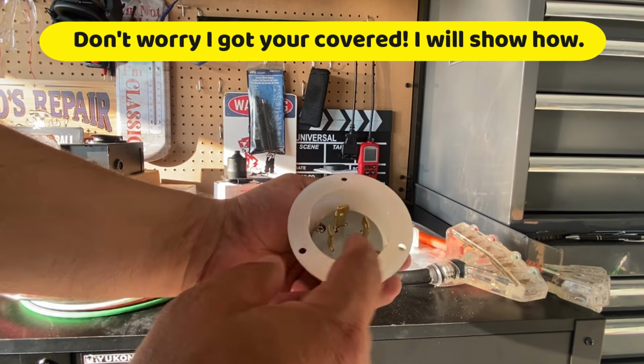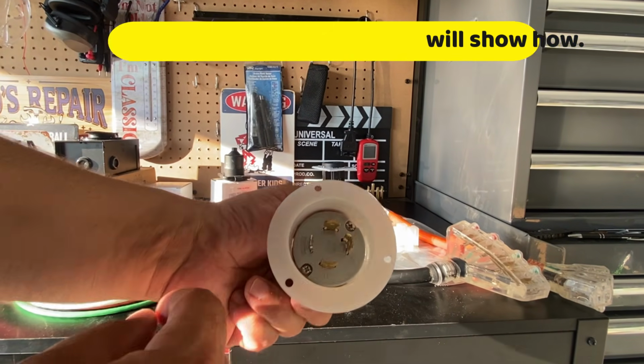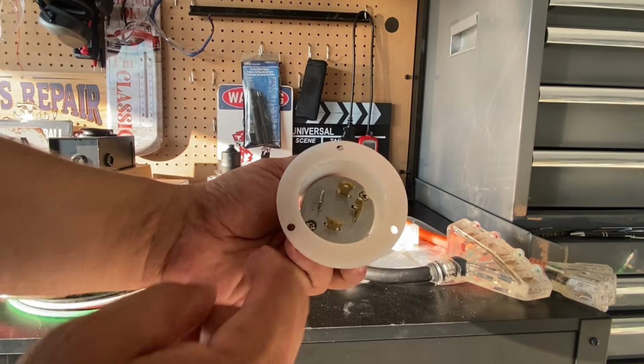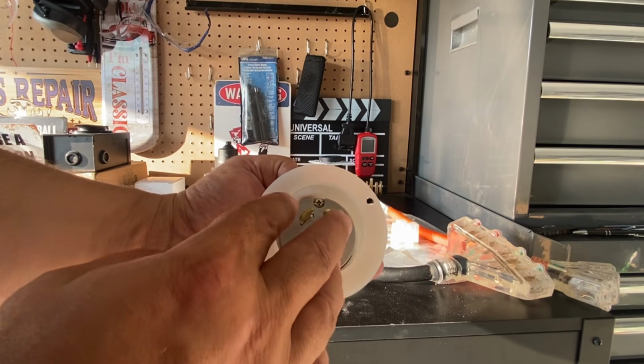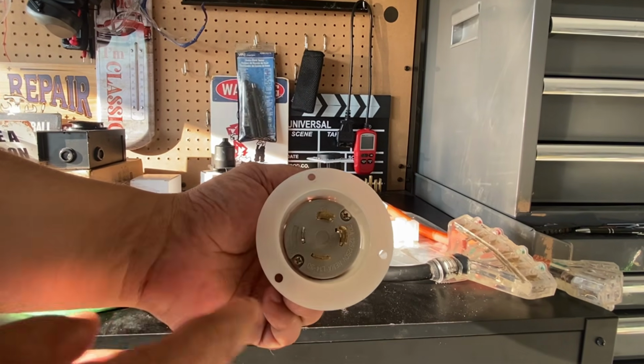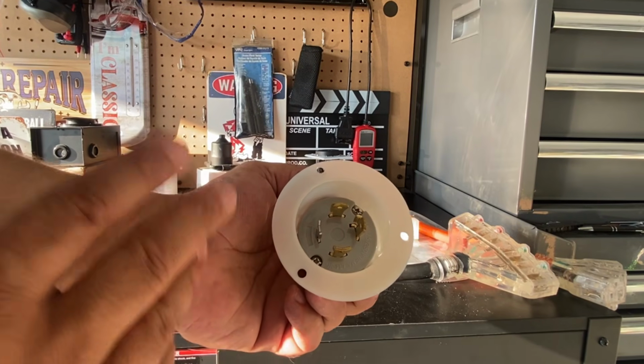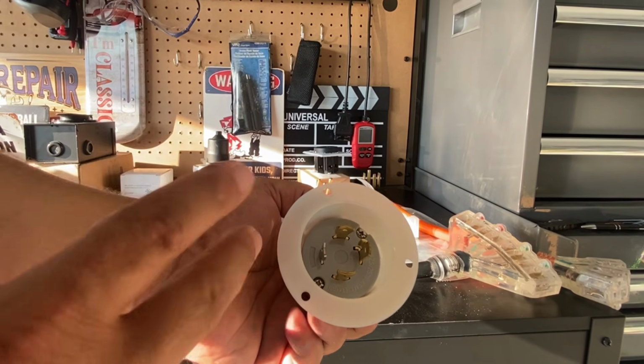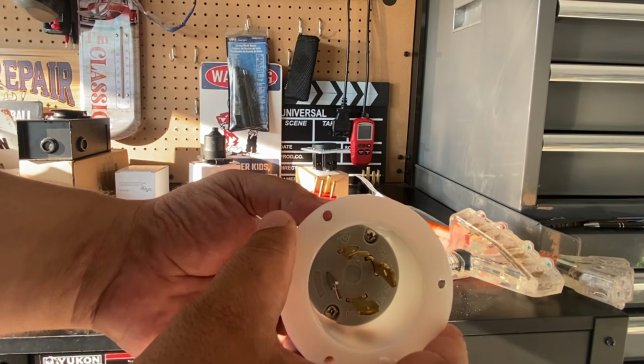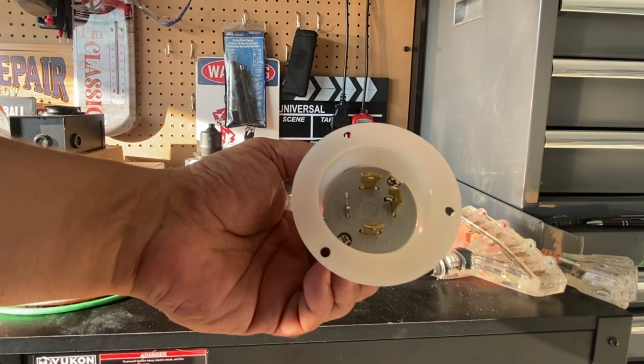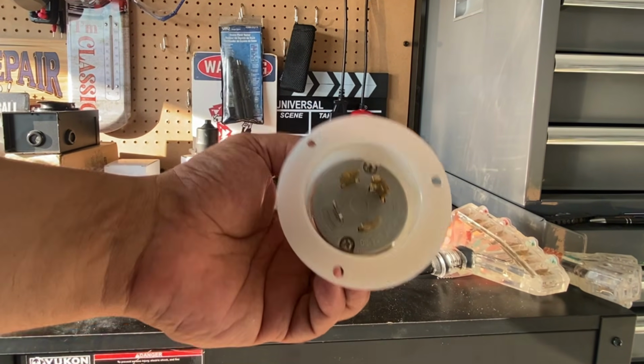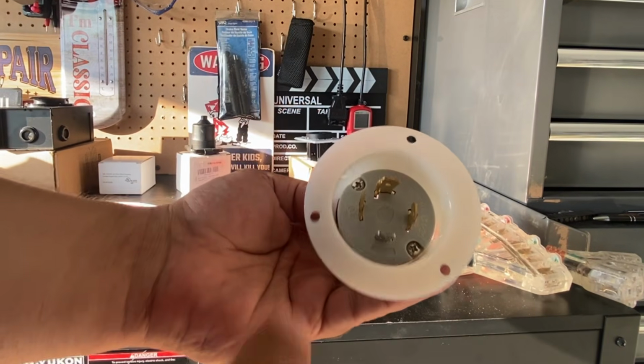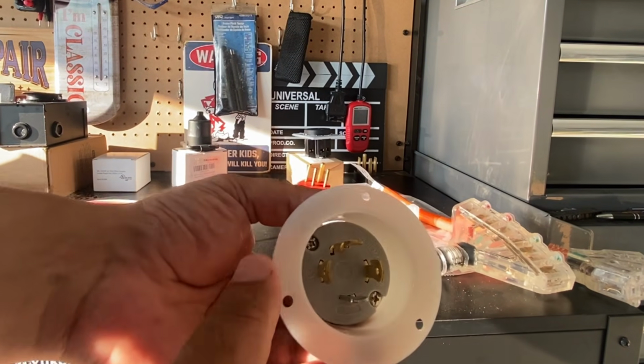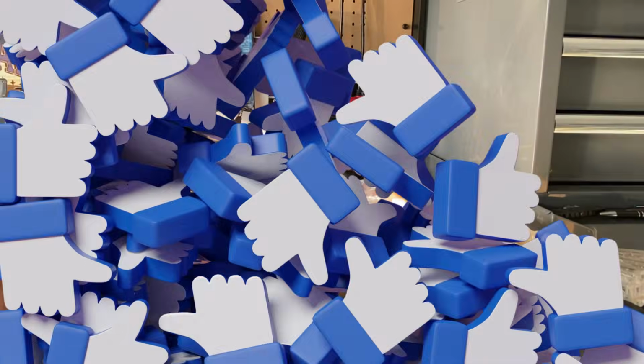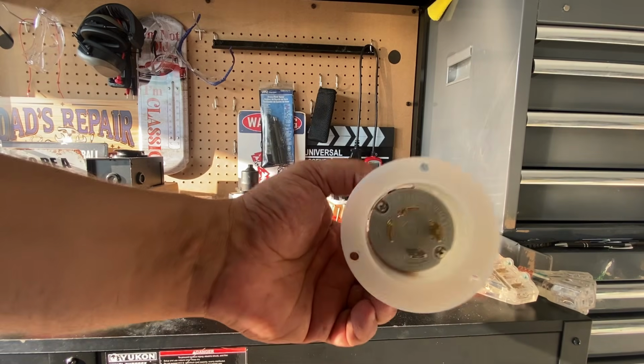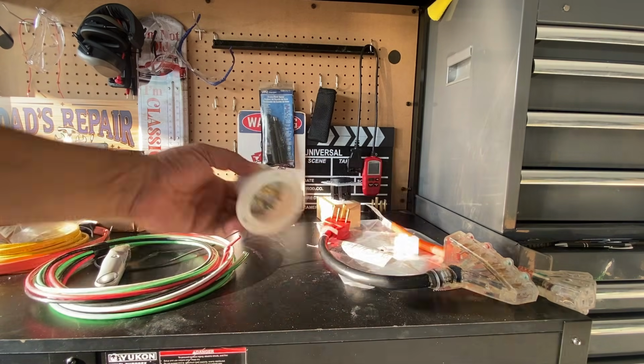The way I did it is to use this right here. This 14-30 connector is a 30 amp connector, so it has 4 connectors, meaning I can put a total of 240 volts, or two 120 volt connections, into the house. That's the route I decided, and this allows me to upgrade in the future. However, they don't make a real receptacle you can just put into a box, so I had to fabricate something to make it work.